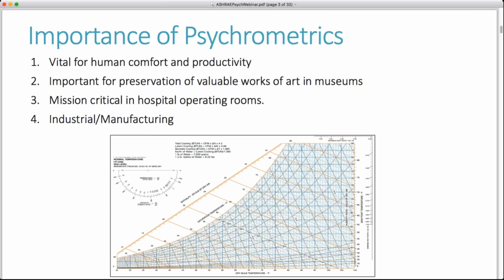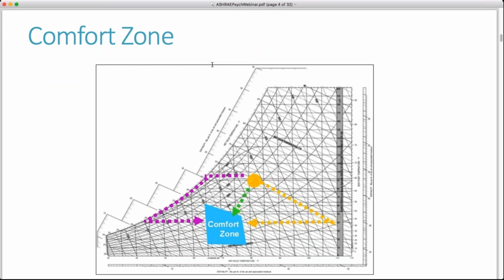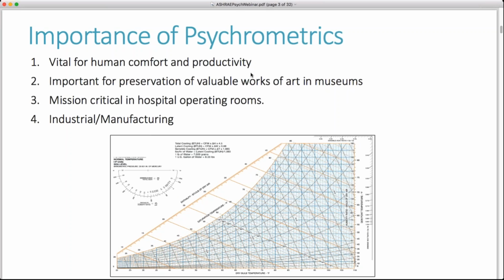So psychrometrics is so important to the design of buildings and in helping engineers design HVAC systems for all types of applications. It's vital for human comfort. It's difficult to work in conditions where it's too humid or too dry. Looking at this psych chart, you'll see there's really a small area where it's actually comfortable for humans to work in. In fact, there's an entire standard called ASHRAE Standard 55, which specifies conditions for acceptable thermal comfort.